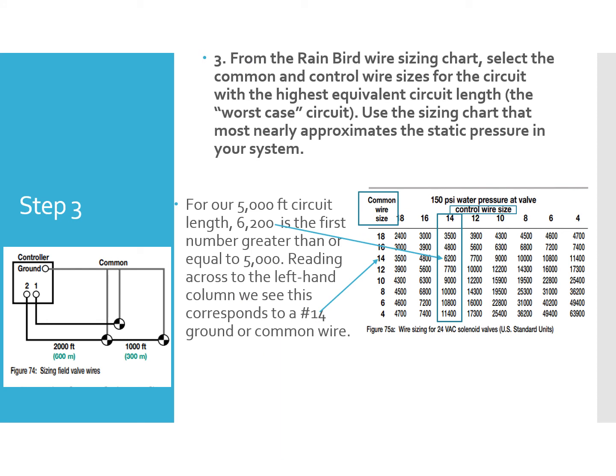Okay, so now from the Rain Bird wire sizing chart, we need to select the common and control wire sizes for the circuit with the highest equivalent circuit length. That was the worst case scenario. So looking at this chart below, we'll see that for our 5,000 foot circuit, the length is 6,200 feet. So what we want to do is try to find the smallest wire that we can use to accomplish this. So we look over here and we're looking for 5,000 somewhere in here. These numbers, remember, the bigger they are, the smaller the wire is. So we don't want to bother looking into these larger size wires here.